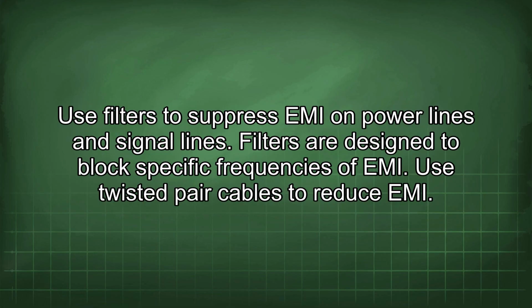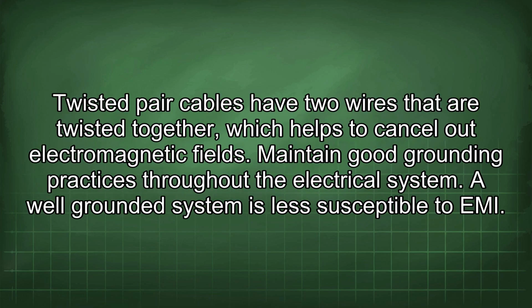Use filters to suppress EMI on power lines and signal lines. Filters are designed to block specific frequencies of EMI. Use twisted pair cables to reduce EMI. Twisted pair cables have two wires that are twisted together, which helps to cancel out electromagnetic fields. Maintain good grounding practices throughout the electrical system. A well-grounded system is less susceptible to EMI.